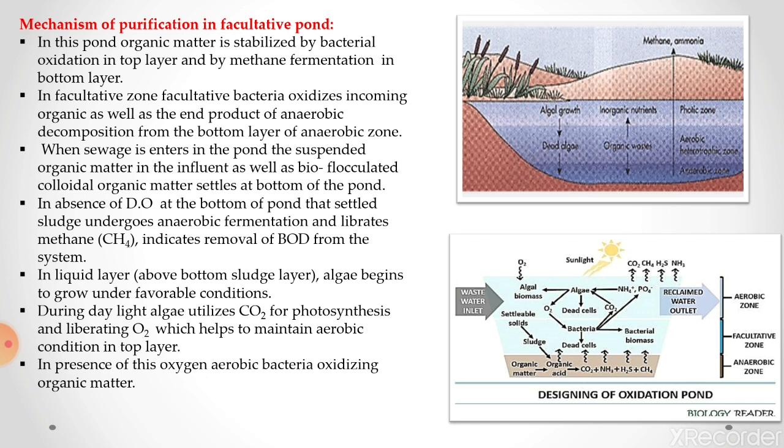There are certain mechanisms of purification in the facultative pond. In this pond, the organic matter is stabilized by the bacterial oxidation in the top layer and by methane fermentation in the bottom layer, as you can see in the figure. In the facultative zone, facultative bacteria oxidize the incoming organic matter as well as the end products of anaerobic decomposition from the bottom layer of the anaerobic zone. When the sewage enters the pond, the suspended organic matter in the influent as well as the bioflocculated colloidal organic matter settles at the bottom of the pond.